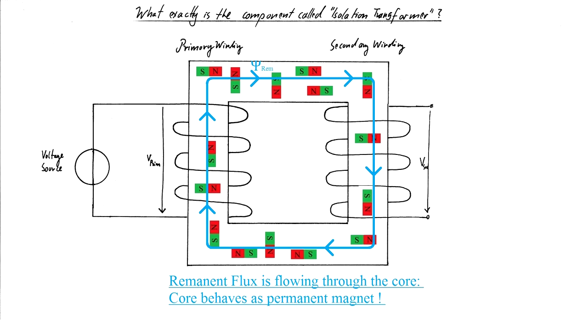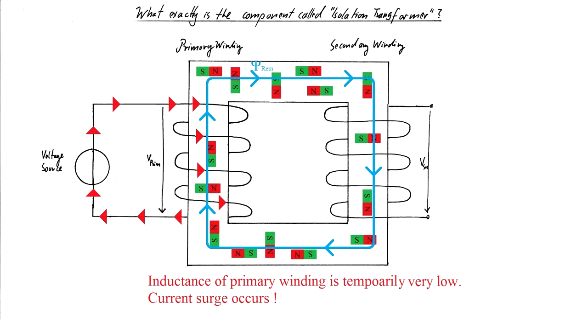The iron core will stay in this state as long as no external magnetic field changes the situation. When the transformer is connected to the grid again, as I did in the footage I just showed you, and it happens that the first half period of the current has the same direction as the last one when the transformer was turned off, the primary winding will try to magnetize the core in the same direction.